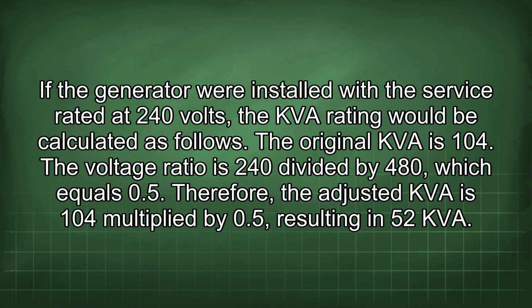If the generator were installed with the service rated at 240 volts, the KVA rating would be calculated as follows. The original KVA is 104. The voltage ratio is 240 divided by 480, which equals 0.5. Therefore, the adjusted KVA is 104 multiplied by 0.5, resulting in 52 KVA.